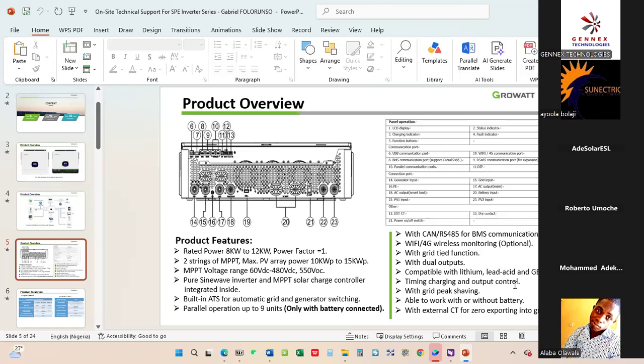Then there is what we call the built-in automatic transfer switch. What does that do? This inverter has the ability to accept the utility power source and simultaneously take that of the generator. That means if you hook up your generator to the inverter, there's a gen port and also a grid port, so there's a switch that transfers automatically. If the generator is operating and there's a failure from the electricity power supply, it will sense that and switch automatically, no human intervention needed. Then you can parallel up to 9 units, that's another good news. Unlike the SPF family, where the maximum is 6.